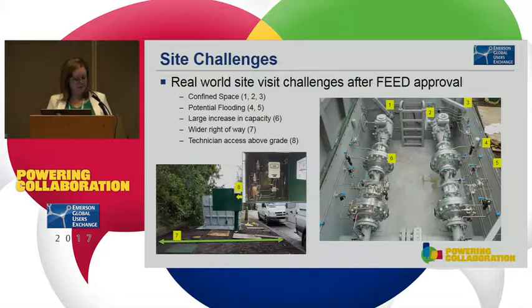And then this is the interesting part — above grade accessibility. Here are the two controllers. For most of the work technicians need to do, they can run their tests from these controllers. There are a few false sensing ports where they can put in extra pressure and run all their functional tests from above grade. They only go into the confined space if there's a problem and they think they need to do maintenance. That's a huge time savings right there.